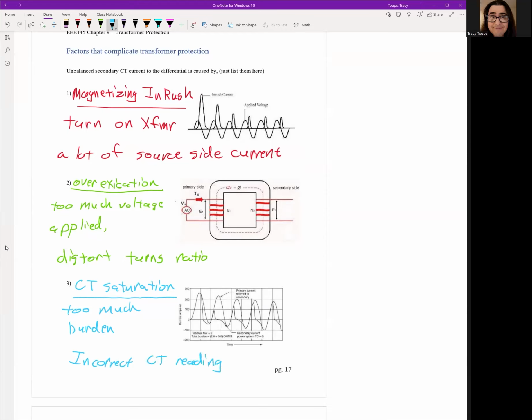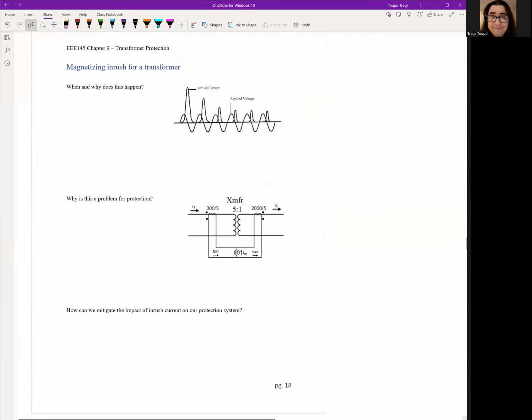Again, the differential relay expects the CT readings to be dead accurate. So if one CT goes into saturation and doesn't keep its CT ratio correctly, you're going to create an imbalance in current, and the differential element might trip offline as well. CT saturation is very prevalent whenever we have very high fault current, because the higher fault currents will cause the CT to saturate quicker. Now we'll say CT saturation, you can't avoid it. It's going to eventually happen. When you have fault current in a CT, there's only so many cycles or seconds it could take before it starts going into saturation. So it's just something we're going to have to live with. Again, especially if you have very high current in your system during a fault.